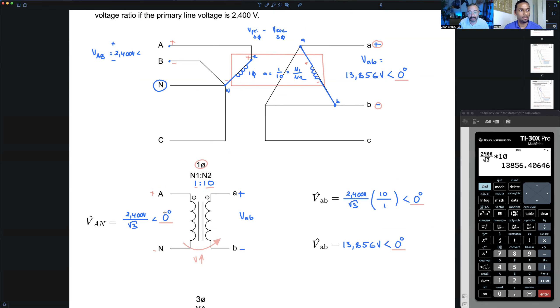Essentially, it's in parallel. So we've got our secondary line voltage magnitude and angle, and our primary line voltage magnitude. We already figured out the three-phase voltage ratio, but let's talk about the phase shift too. Earlier, I asked you to pick the easiest angle for A to neutral on the Y side, and you said 0 degrees.